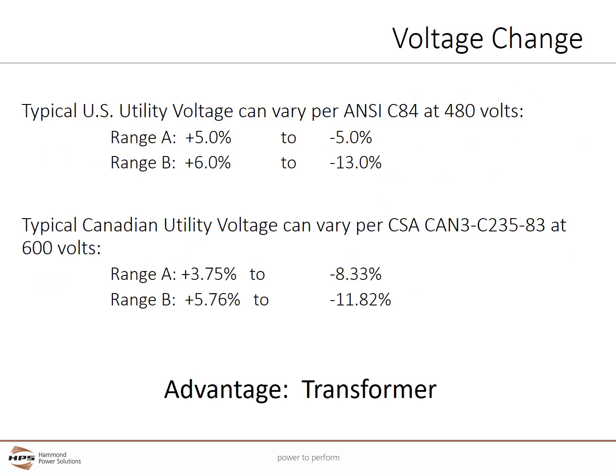Users should remember that facilities are not always supplied with exactly the voltage needed, such as 480 or 600 volts. In both the US and Canada, range A is ideal and typical, but not always possible or practical. Range B voltages necessarily occur in practical design and operating conditions on the supply or user systems, or both. However, it should be recognized that because of conditions beyond the control of the supplier or user, or both, there will be infrequent and limited periods when sustained voltage is outside of even range B limits. Utilization equipment may not operate satisfactorily under these conditions, and protective devices may operate to protect the equipment. Again, only a transformer can react to situations like this.